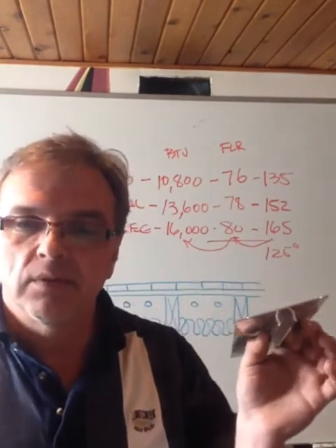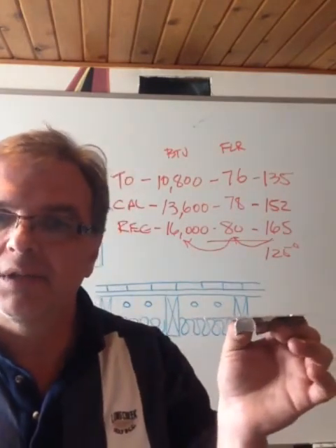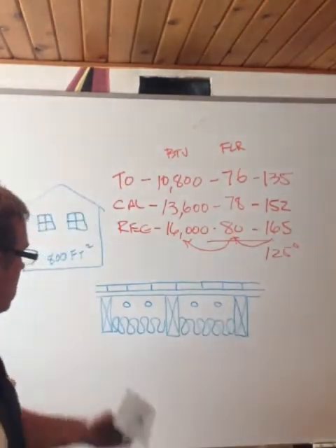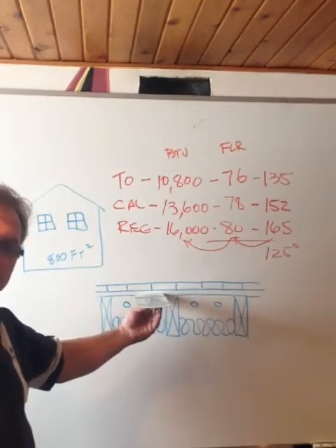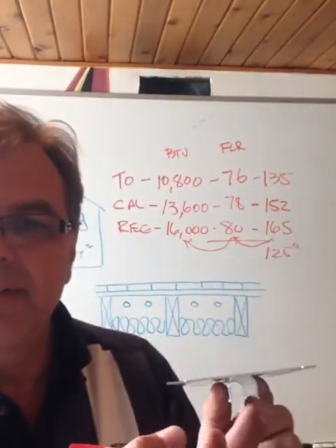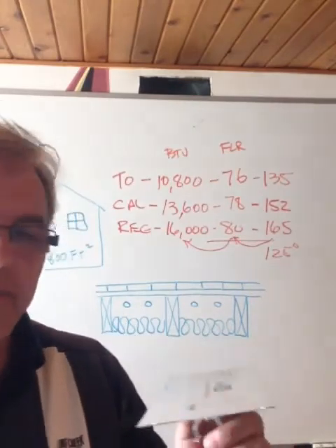Well, what you need to do in a cold climate like Saskatchewan is add heat transfer plates. Okay, you would put 2 down each joist cavity, screw them to the underside of the floor, snap your tubing in this little groove here, and away you go.